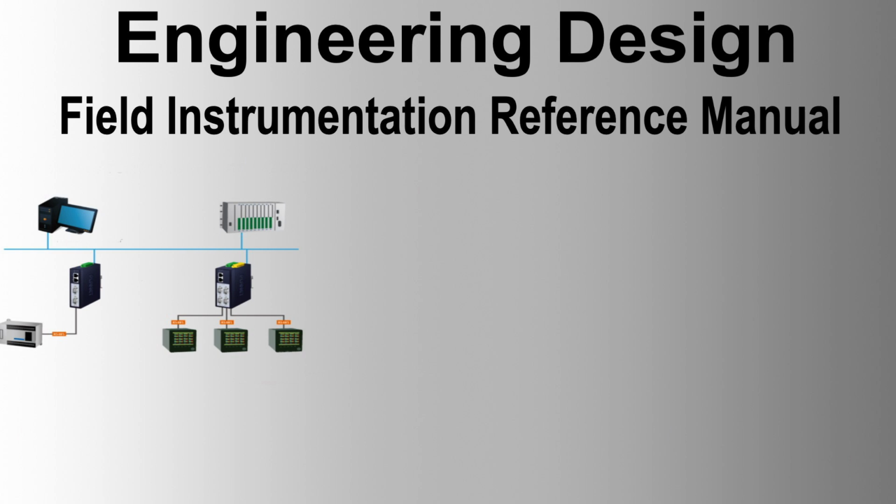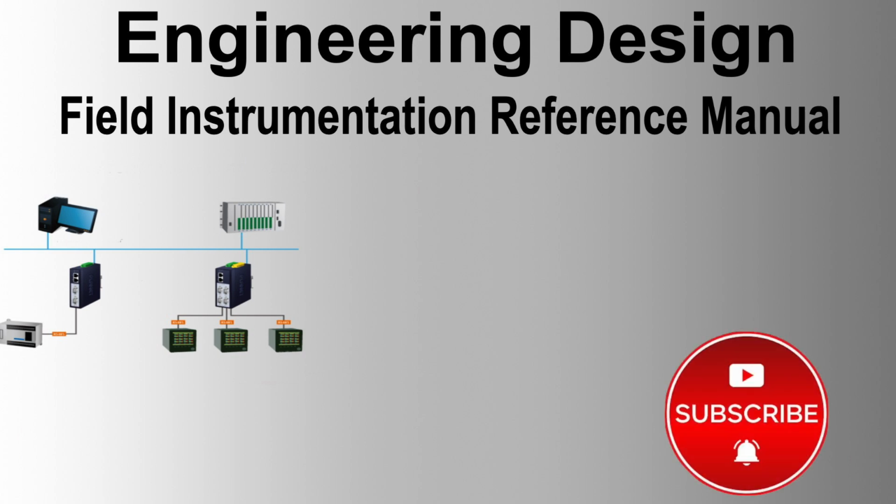Steps for instrument selection. 1. Identify operating cases. Consider all operating scenarios such as normal operation at minimum, normal, and maximum flow, alternative operating modes, startup, commissioning, and emergency operation.